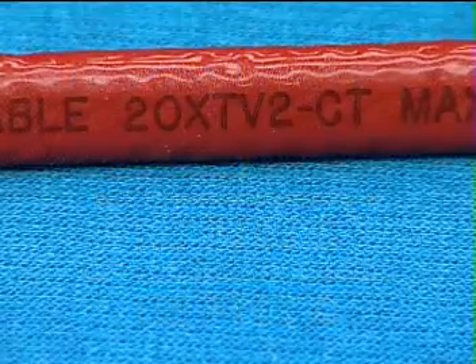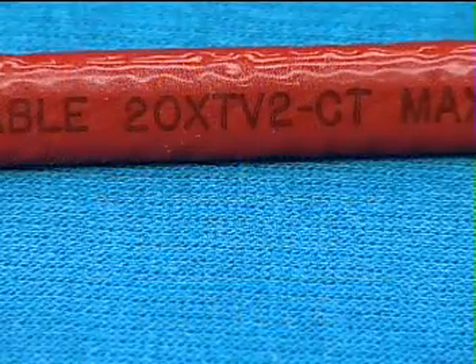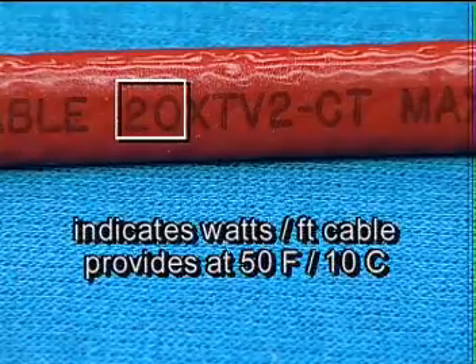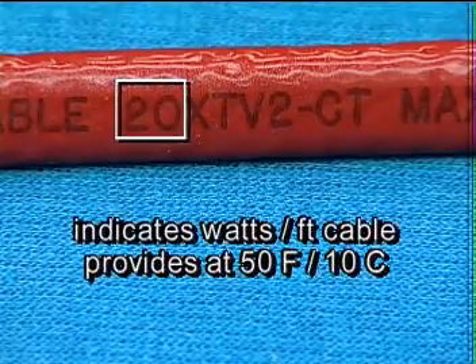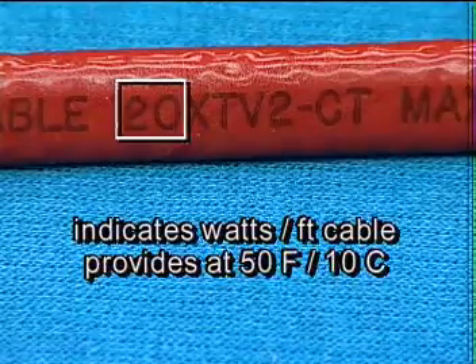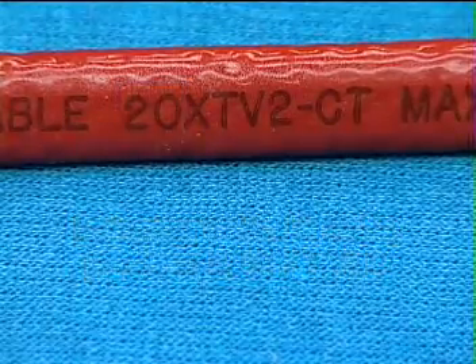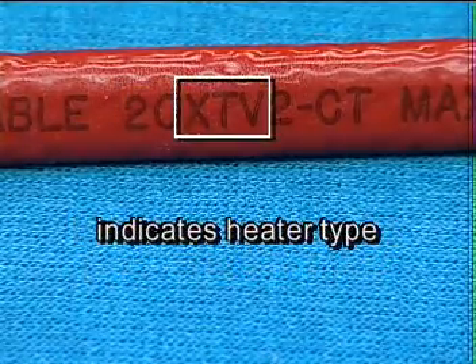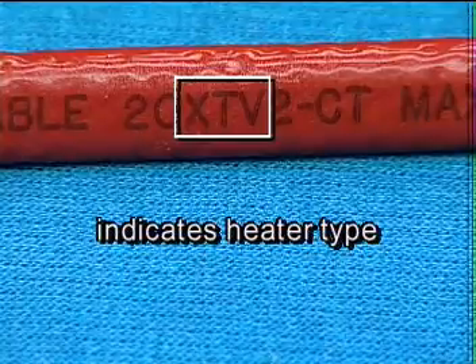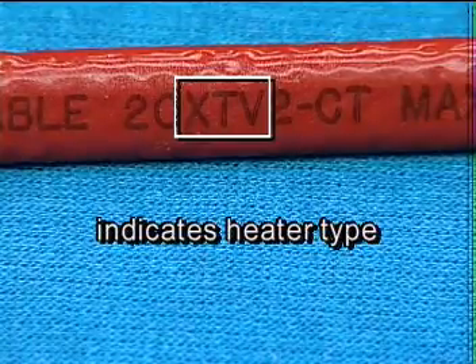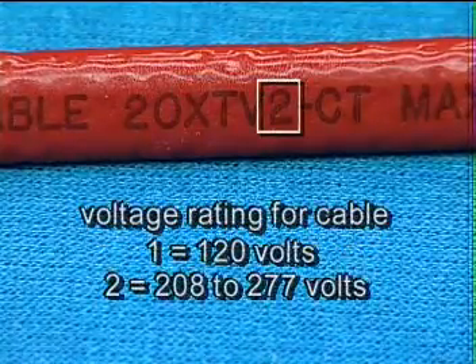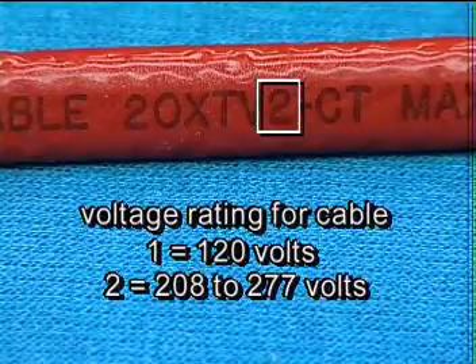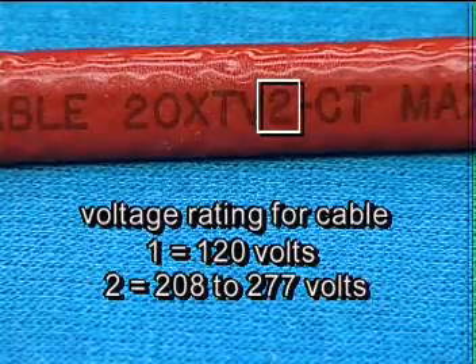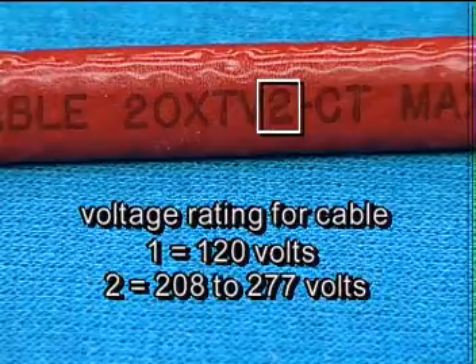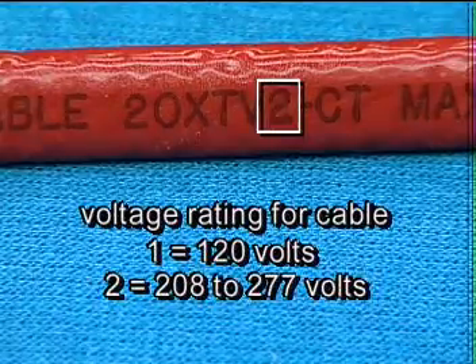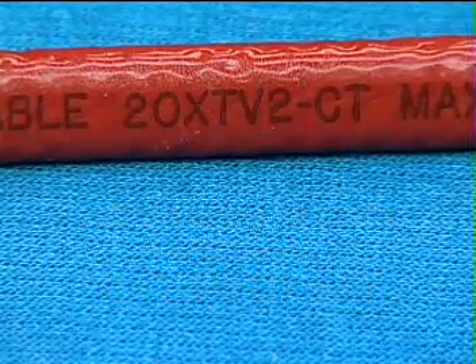The cable catalog number is printed on the outer jacket of every cable. The first number indicates the watts per foot the cable provides at 50 degrees Fahrenheit, 10 degrees Celsius. Next is the heater type, XTV, KTV, QTVR, or BTV. Next is a voltage rating for the cable. A 1 indicates 120 volts, and a 2 indicates 208 to 277 volts.